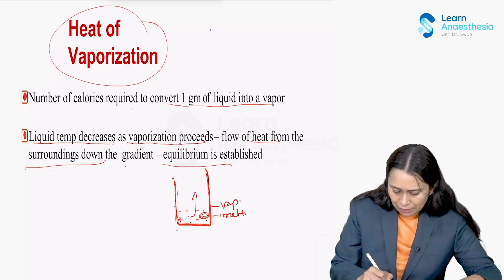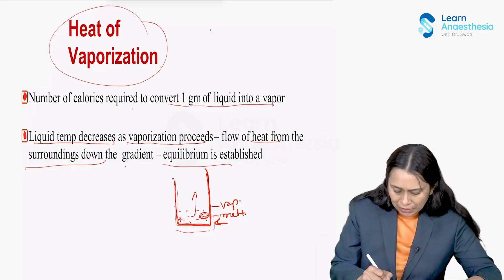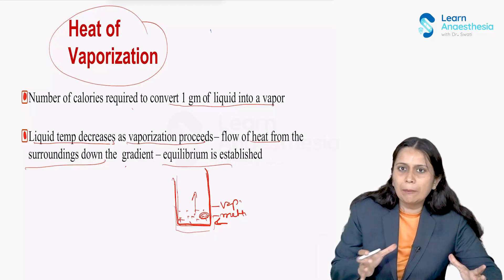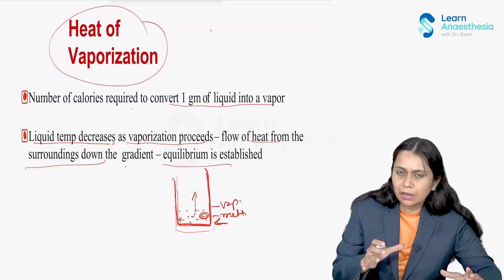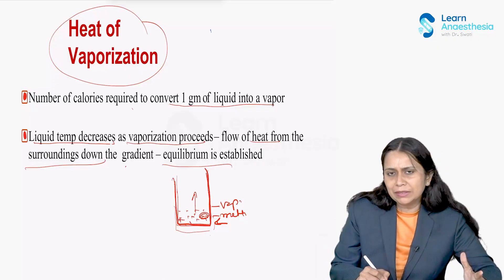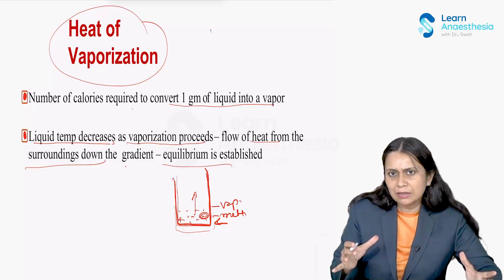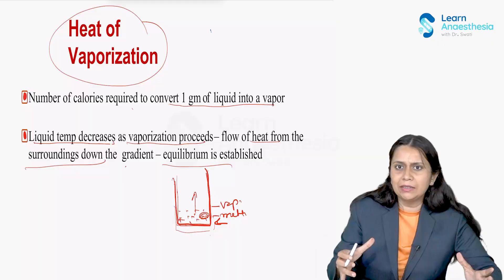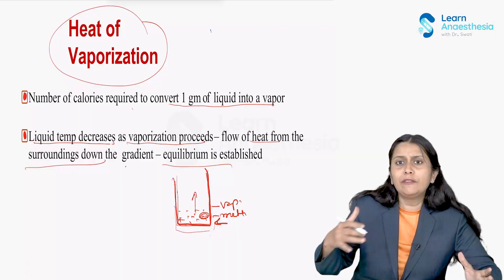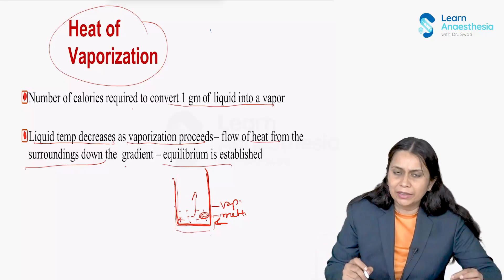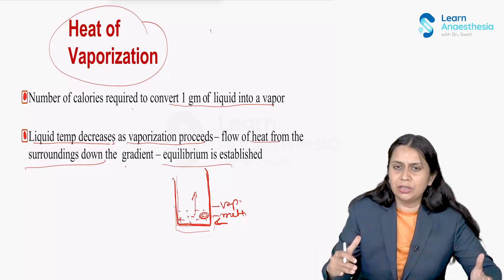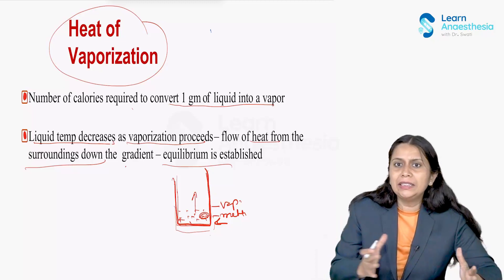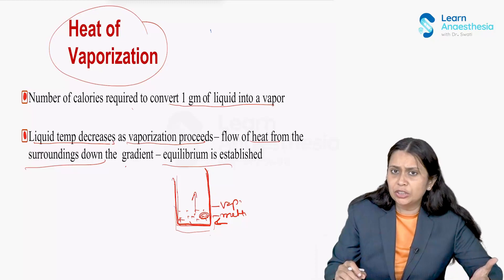The equilibrium is achieved by maintaining a heat bath — either by external supply of heat or by the metal which makes up the vaporizer. This heat loss is compensated, but only at a finite level. When cooling happens and temperature fluctuates, there should be a compensatory mechanism to compensate for this heat loss so that the vapor output in the total gas is not affected. Because of this heat of vaporization, we need something called temperature compensation in designing the vaporizer.